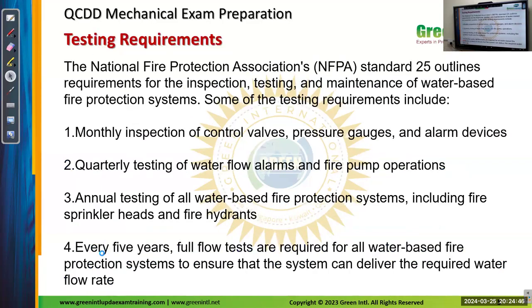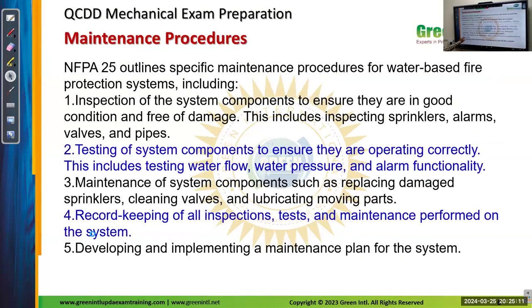So, testing requirements. NFPA outlines the requirements for testing. It gives a monthly inspection of control valves, pressure gauges, and alarm devices, quarterly testing of water flow alarms and fire pump operations, and annual testing of all water-based systems, including sprinkler heads and fire hydrants. Every 5 years, water-based systems should be checked to ensure they deliver the proper flow rate. So, for sure, you can expect 2 or 3 questions from this topic. The weightage will be 6 or 7 marks. Okay? Inspection, testing, and maintenance.